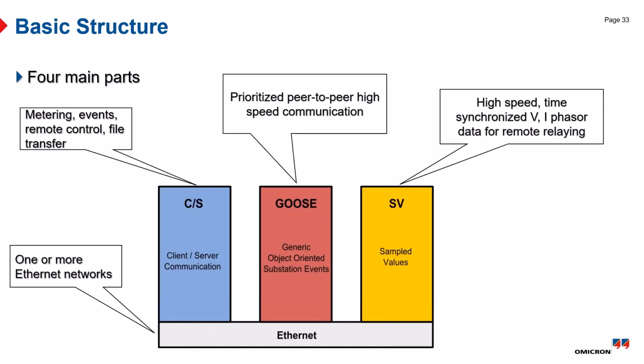And then finally, on the other side, you see client server. Client server is just like it sounds. You have a client and you have a server. So say the control center can make a query to a device, and the device answers. The control center can issue a command, tell a breaker to close. That will be done via client server. So 3 different services, 4 different parts. This is the basic structure of 61850.